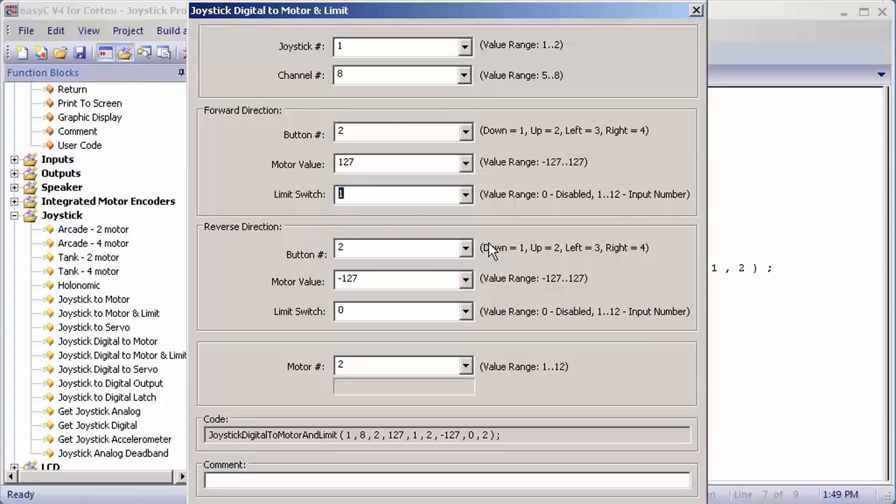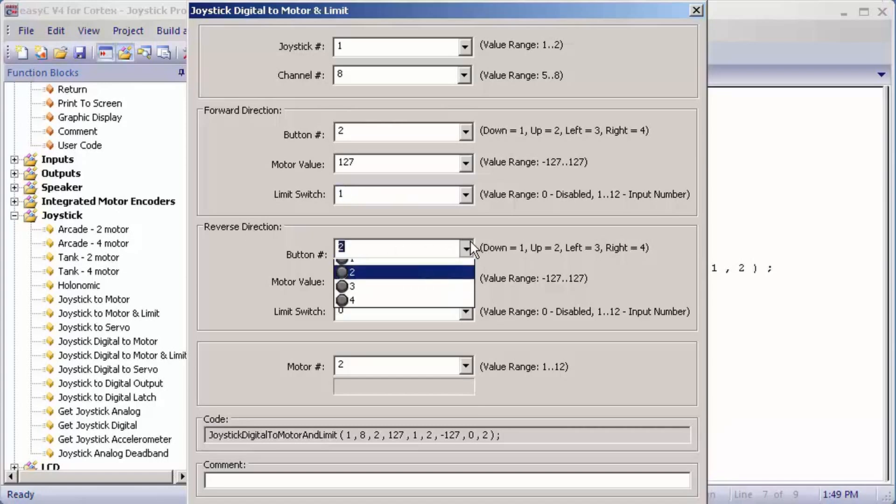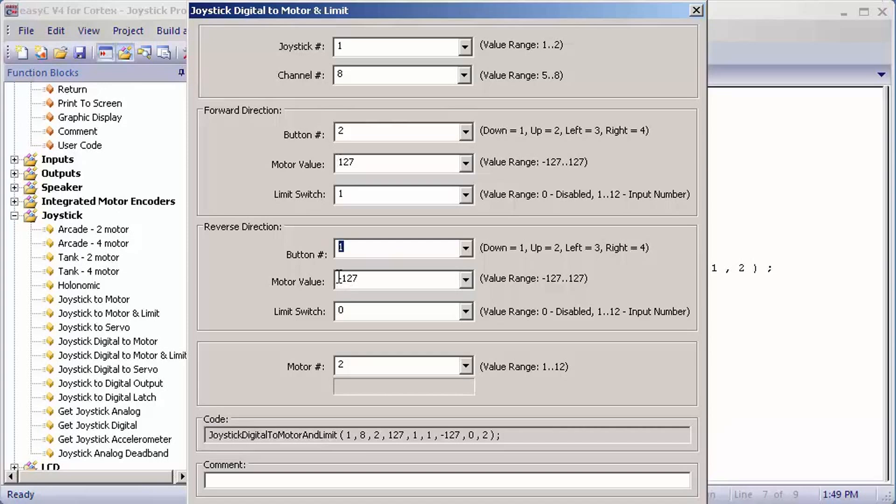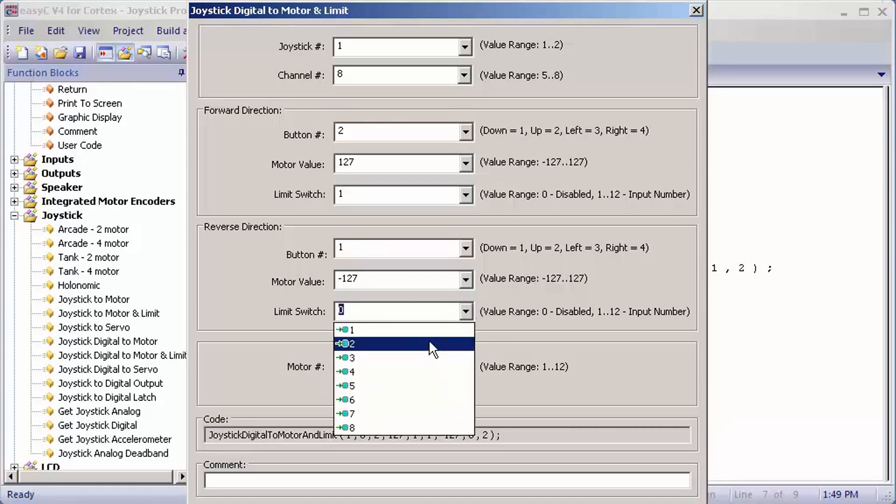For reverse direction, you're going to pick the opposite of your forward direction. Instead of being up, we're going to select down, so one. For motor value, it's going to be inverted, it will be negative. But if it was negative here, you would make it positive there. For limit switch, you would pick your negative limit switch, so I'm going to pick two.